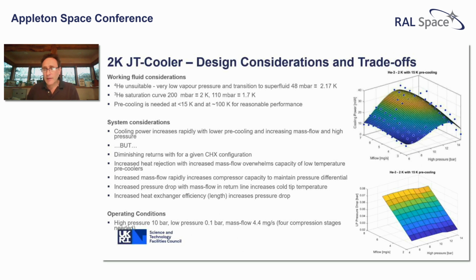It's very different - a very brief run through some of the design considerations. The working fluid, first of all, is important. It's unsuitable to use helium-4 for this cooler, it has an extremely low vapor pressure and transitions to a superfluid at 2.17 K. So instead we're using helium-3, and on the saturation curve, 200 millibars is equivalent to 2 K, which allows us to reach those temperatures.